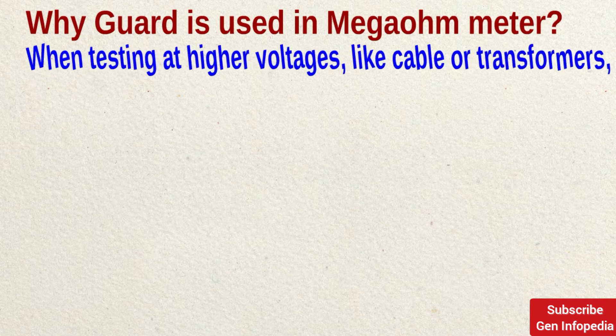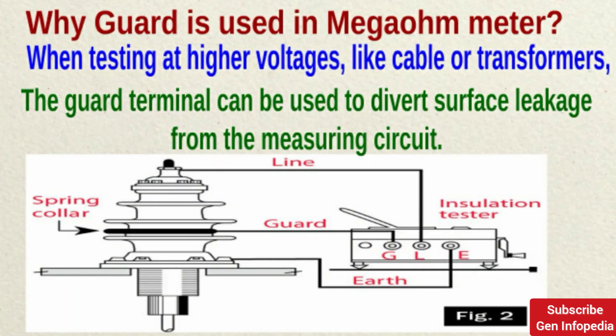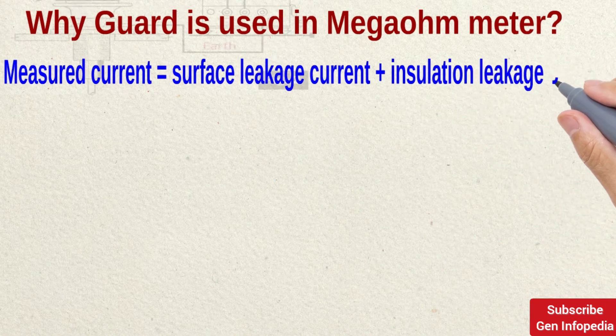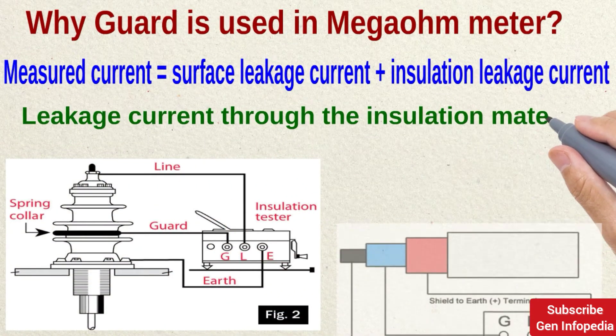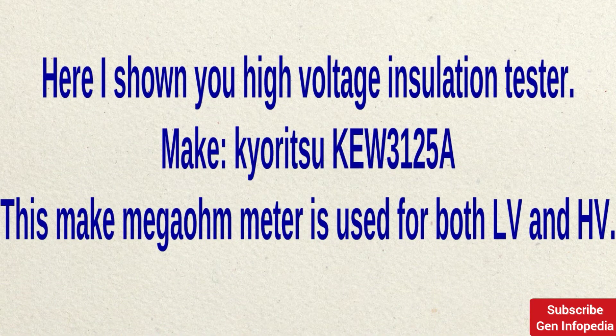Everyone may have a doubt about why the guard terminal is used. When testing at higher voltages — such as with cables or transformers — the guard terminal diverts surface leakage current away from the measuring circuit. For example, if you are performing a primary-to-ground test on a transformer, you need to guard the secondary windings. This guard connection provides a return path for surface leakage current. Without connecting the guard terminal on HV equipment, it creates errors. The measured current equals surface leakage current plus insulation leakage current.